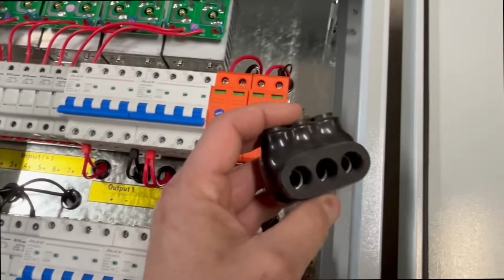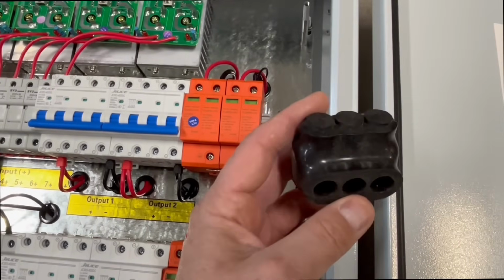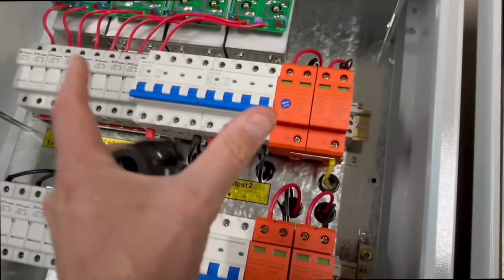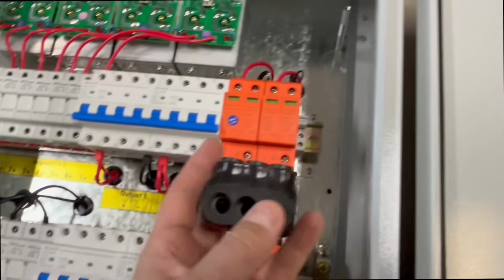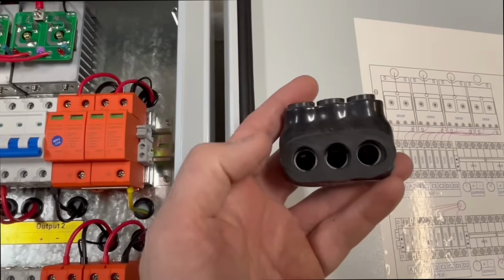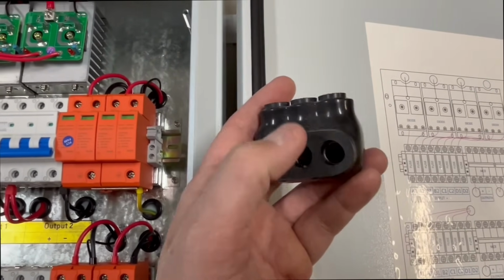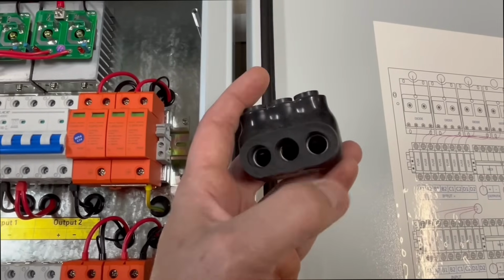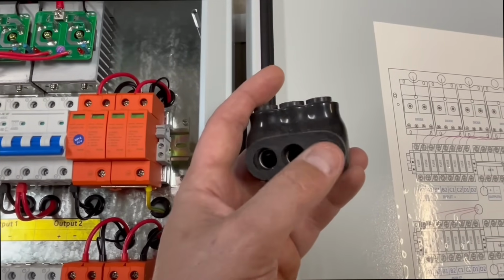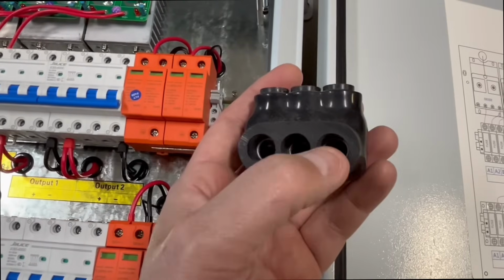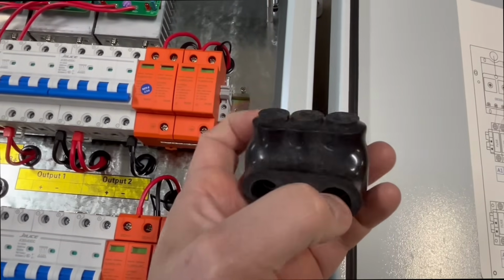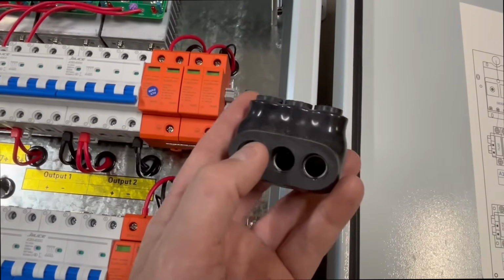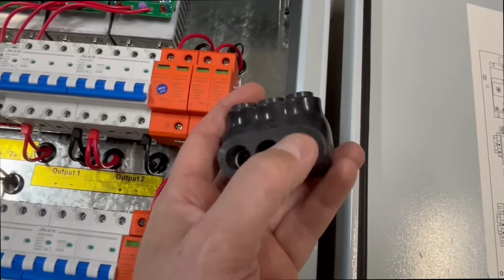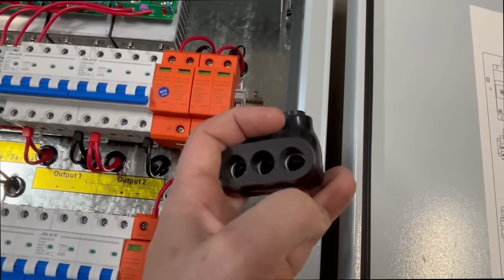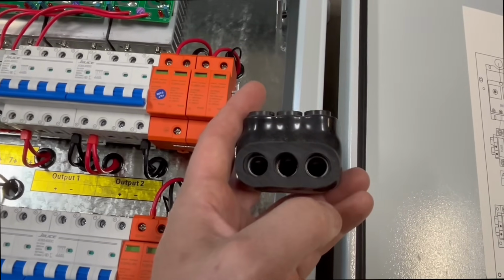You could actually look at it like this, if you guys have ever seen these three-way Polaris splices. The combiner box is going to be doing the same thing essentially. It's going to be combining string one, string two, and then the string coming out will be going to your inverter. But because you're paralleling, it's going to be double the amperage. The voltage is going to stay the same, but this third leg, as it goes out to the inverter, is going to have double the amperage.